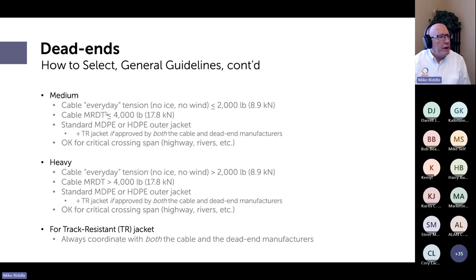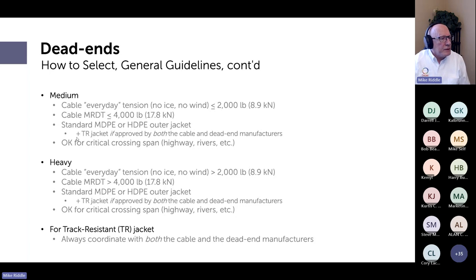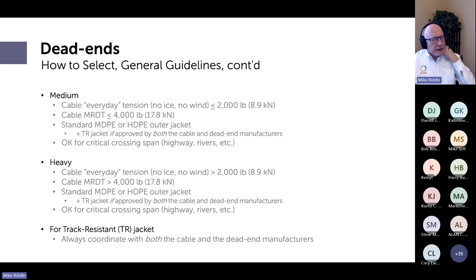Medium duty dead ends: cable everyday tension less than 2,000 pounds, MRDT less than 4,000 pounds, medium density or high density outer jacket, and if it's a tracking resistant jacket it's acceptable if approved by both the cable and dead end manufacturers. Medium duty dead ends are okay for critical crossings.